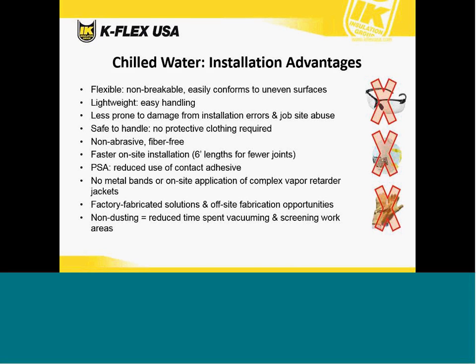There are some advantages to using elastomeric insulation on chilled water systems. It's flexible, it's non-breakable, and it easily conforms to uneven surfaces. It's light and easy to handle. It's resistant to damage from installation errors and job site abuse. It's safe, with no protective clothing or respirators required. It's dust and fiber free.